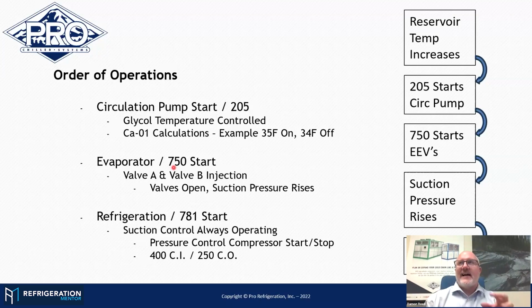So I added in the compressor control. That's one of the things I didn't really get deep into, like the medium temp capacity control. I'm not getting deep into flash gas control, my high pressure valve control, my heat recovery control. All that's still happening off to the side. But at its simplest level, the circ pump starts based off of temperature. That wakes up my evaporator. That then turns on my refrigeration control. This is how I get a compressor and expect to see a compressor operating.